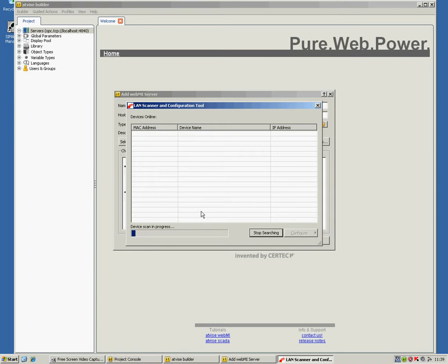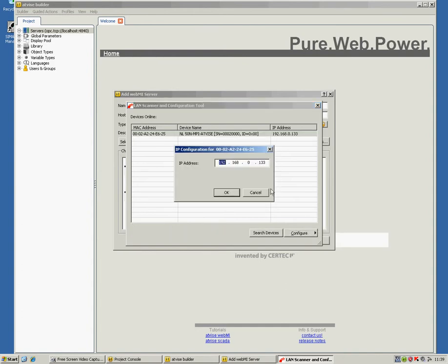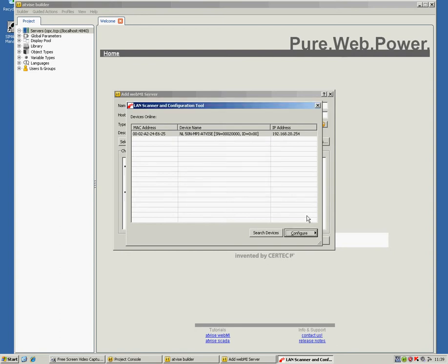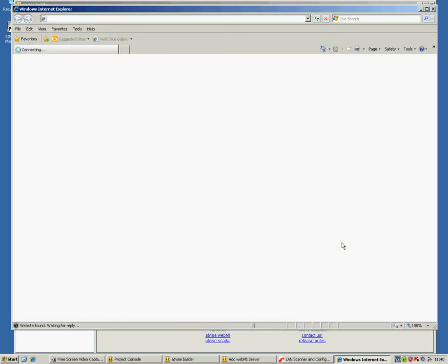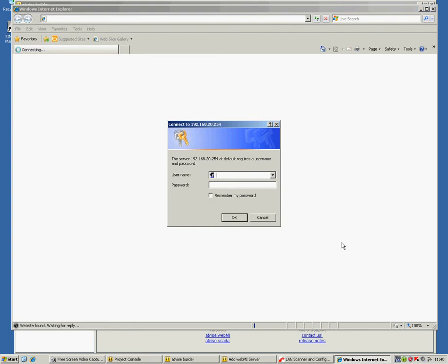First, we have to set up the IP address of our netLINK SCADA device. By default, the netLINK SCADA device has an IP address that usually does not fit to your IP network. Therefore, you have to choose Configure Set Temporary IP Address. It's the same with me, so I'm changing it to the right one. Since the device has now a reachable IP address, we can now select a second option to set the IP address now permanently.